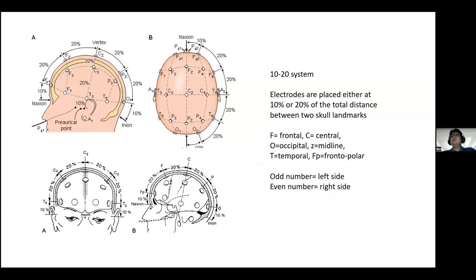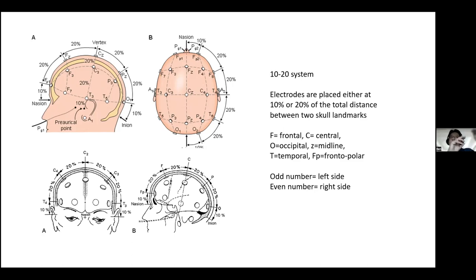For electrode placement, there is the 10-20 system, referring to percentages. It's not a direct measurement because everyone's head is different — the same applies to pediatric versus adult patients. They use anatomical landmarks: for instance, from the nasion and inion. If the distance is 40 cm, then 10% of that is 4 cm, and from there they place the electrodes.